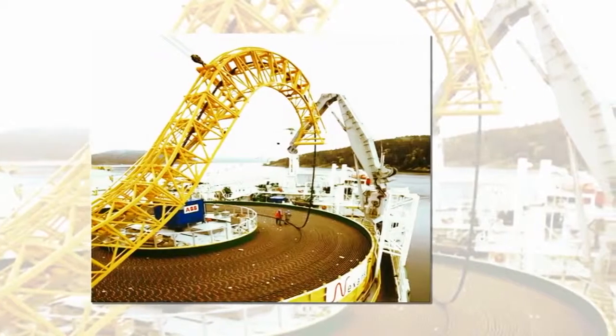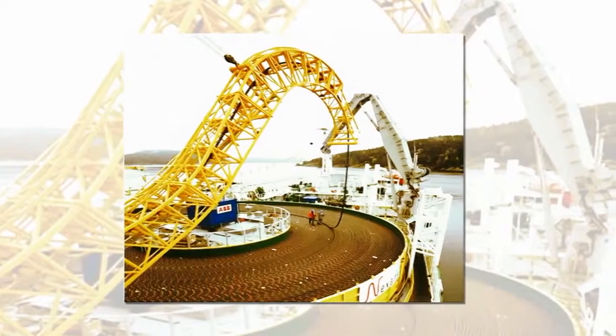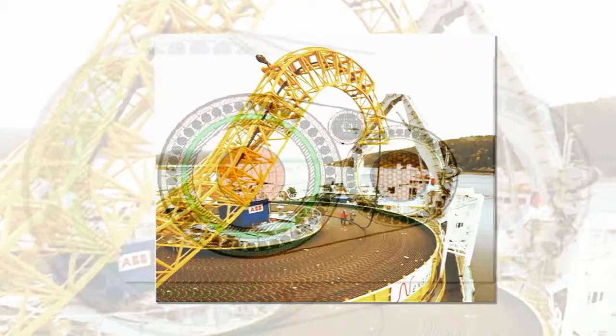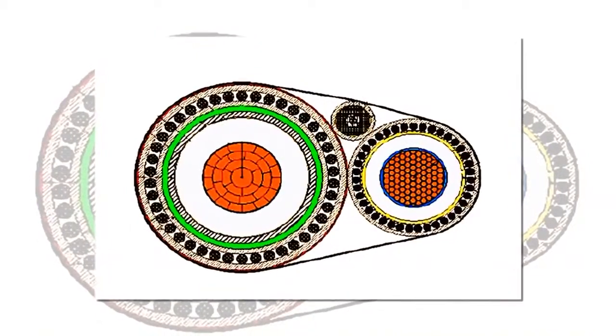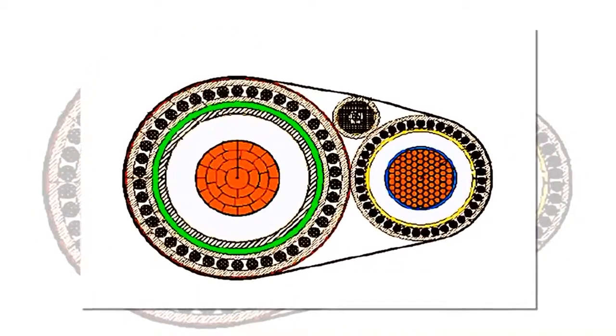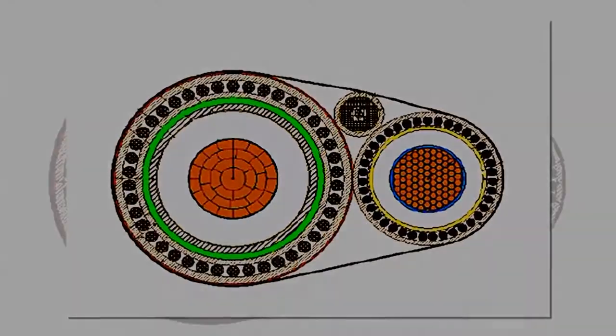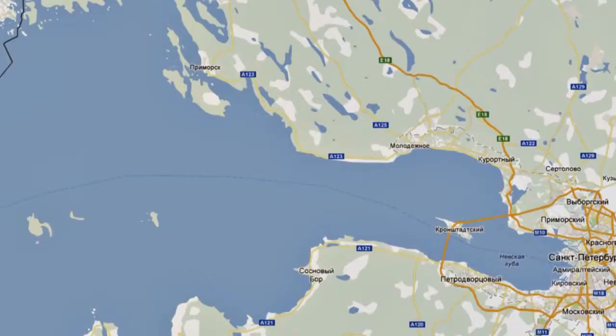At the Vyborgskaya substation, an inverter substation will be constructed within the next 2 years. It will convert DC transmitted by the lines into AC, alternating current. Rated transmission capacity is 1000 MW at ±300 kV voltage, with current strength of 1700 amperes.